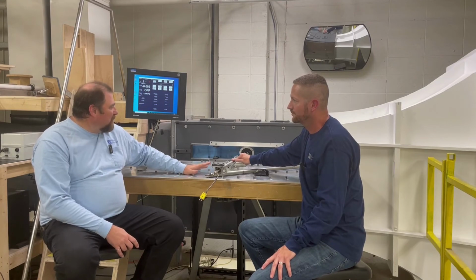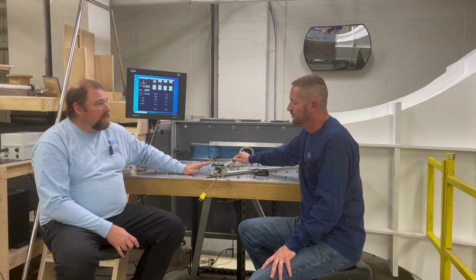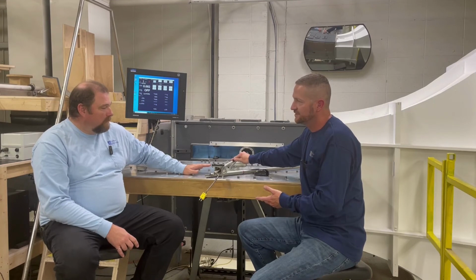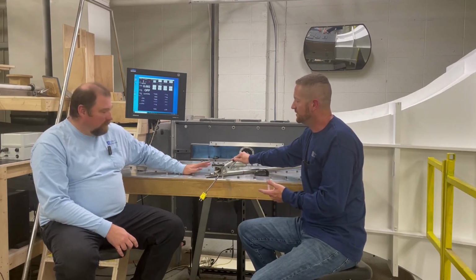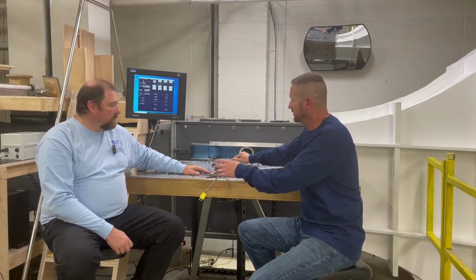Roughly how many velocities do we actually calibrate these at? We would do three velocities for the flow: 30, 60, and 90 feet per second.